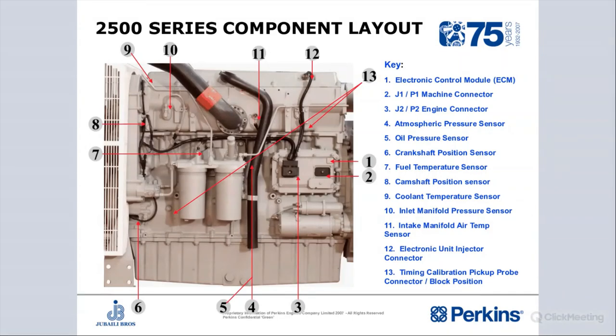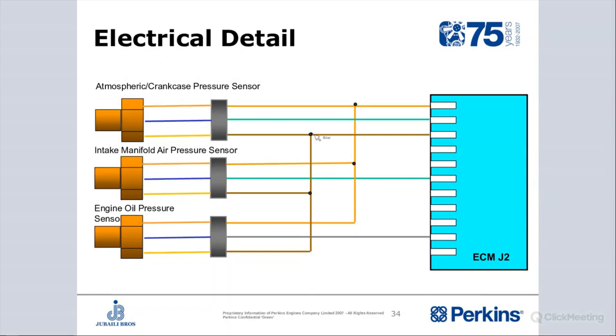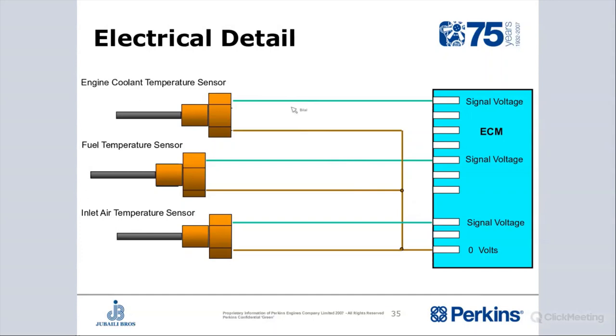Let's talk about the first one. That's how it looks like. It has three wires connected to it. That's how we distinguish between sensors, whether they are pressure reading sensors or temperature reading sensors. On the pressure reading sensors, we have three wires connected to the sensor. The temperature reading sensors only have two wires connected. That's how we can distinguish between both types.